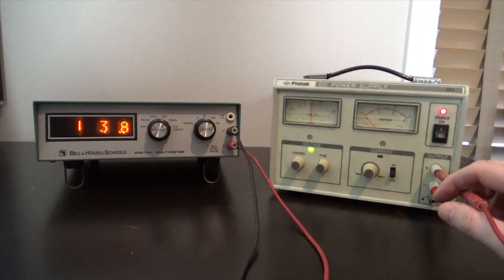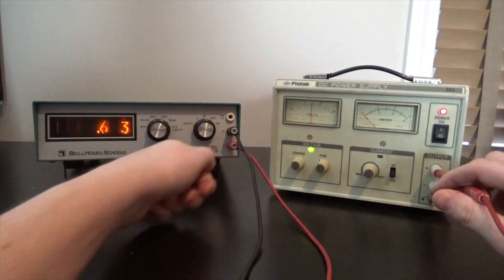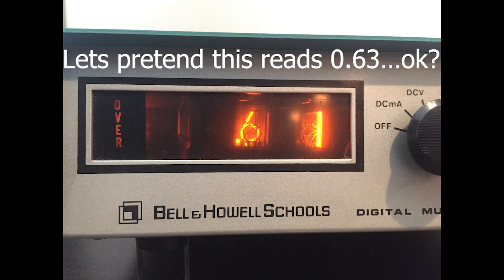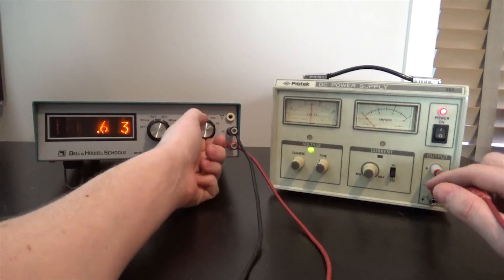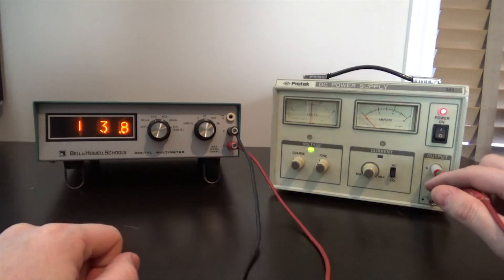An interesting thing about this one is if we change our range, you see we have an over light. That tells you that you need to change your scale. And then the one will come in showing 13.8.